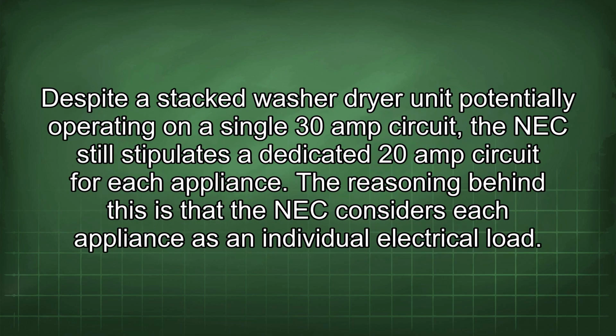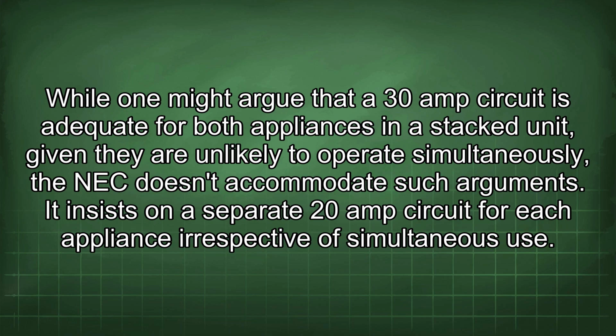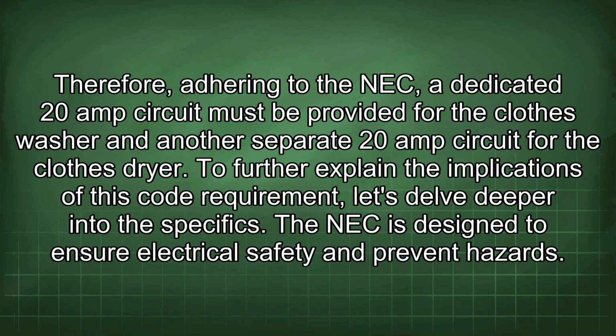Despite a stacked washer-dryer unit potentially operating on a single 30-amp circuit, the NEC still stipulates a dedicated 20-amp circuit for each appliance. The reasoning behind this is that the NEC considers each appliance as an individual electrical load. While one might argue that a 30-amp circuit is adequate for both appliances in a stacked unit, given they are unlikely to operate simultaneously, the NEC doesn't accommodate such arguments. It insists on a separate 20-amp circuit for each appliance irrespective of simultaneous use. Therefore, adhering to the NEC, a dedicated 20-amp circuit must be provided for the clothes washer and another separate 20-amp circuit for the clothes dryer.